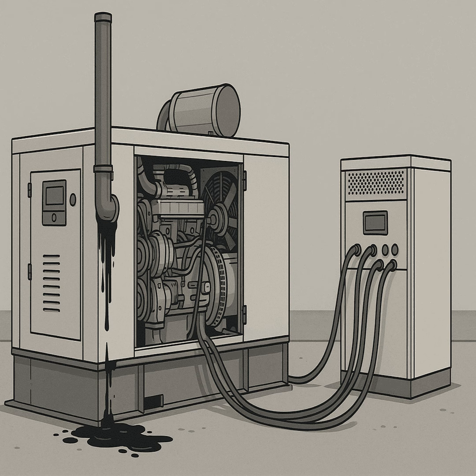And think about modern diesel generators. Many have sophisticated after-treatment systems to meet emissions regulations, things like diesel oxidation catalysts, or DOCs, selective catalytic reduction, SCR systems, diesel particulate filters, DPFs. Right, all that complex tech. Well, these systems are very sensitive to operating conditions. They often need specific high exhaust temperatures to work correctly. Low-load operation and wet stacking prevent them from reaching those temperatures. So you could fail emissions tests. You could absolutely fail emissions tests, yeah. It can cause the after-treatment systems to become clogged or ineffective, leading to compliance issues and potentially more repair costs.